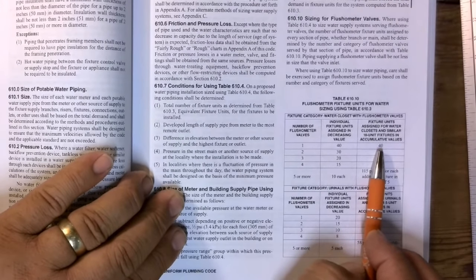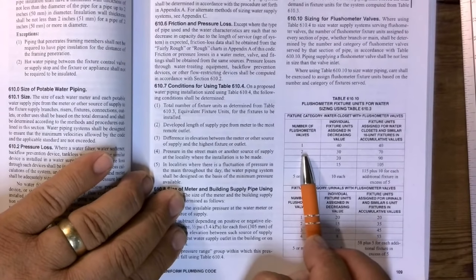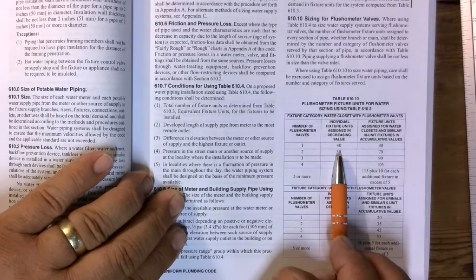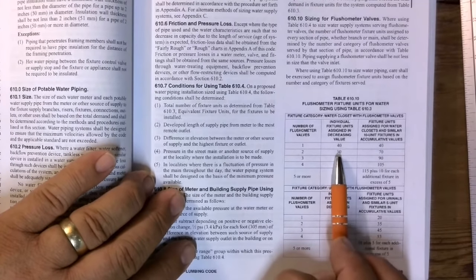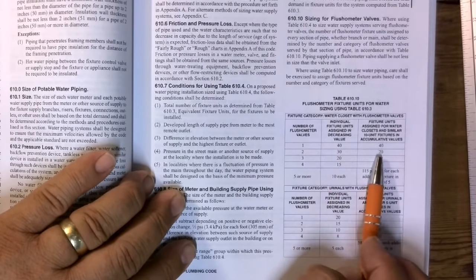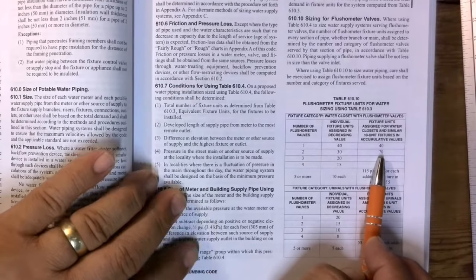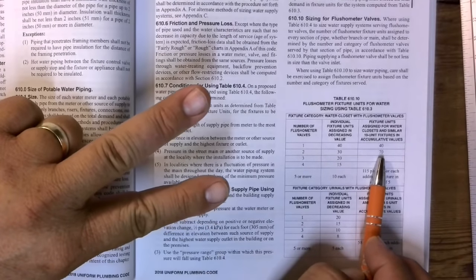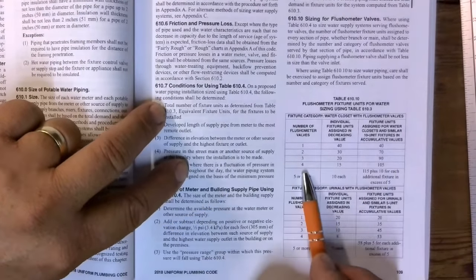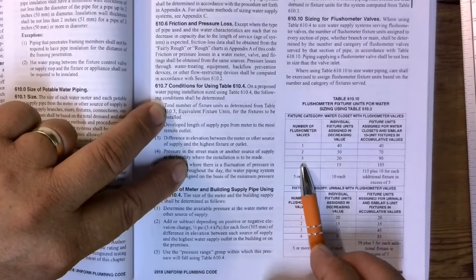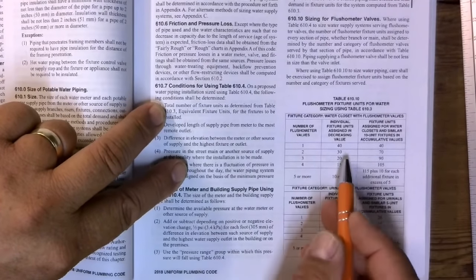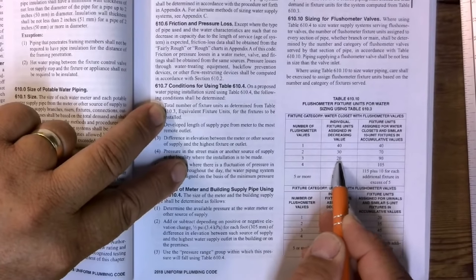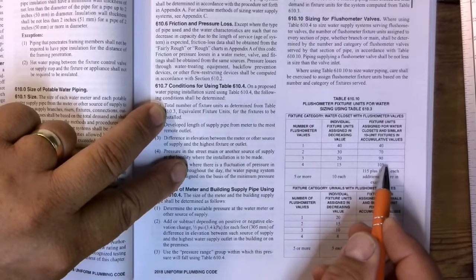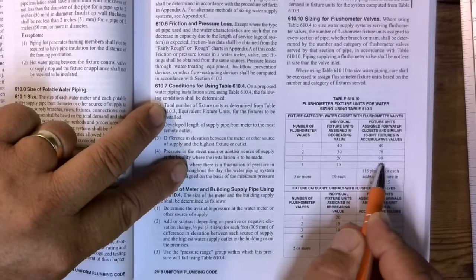But what if I have two flushometer valves? The individual fixture units are assigned in decreasing value. So the first one is 40, the second one is 30, which gives you a total fixture unit value of 70 on that piece of pipe feeding two flushometers. What if I have three flush valves? First one's 40, second one's 30, third one's 20, which gives me a total of 90 fixture units.